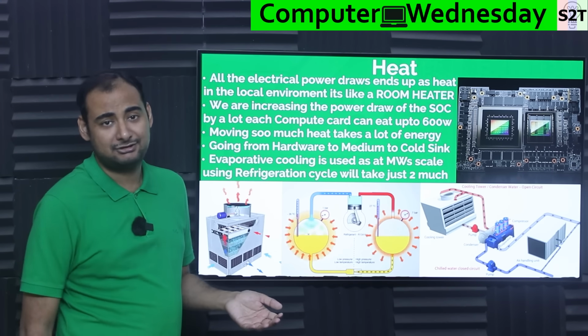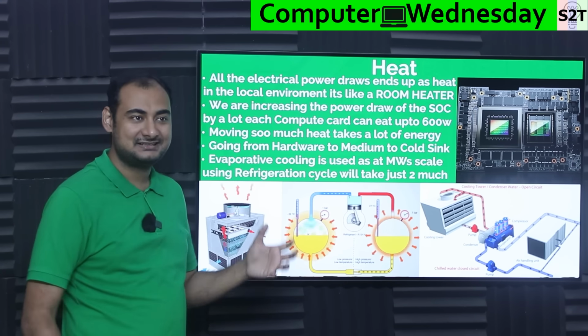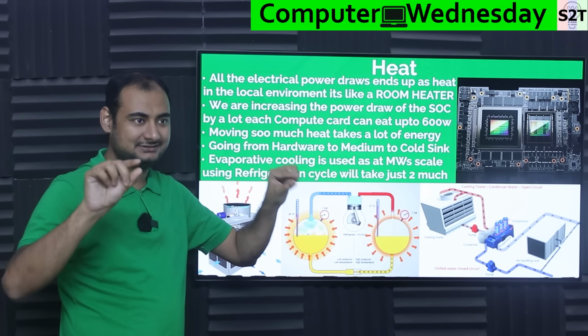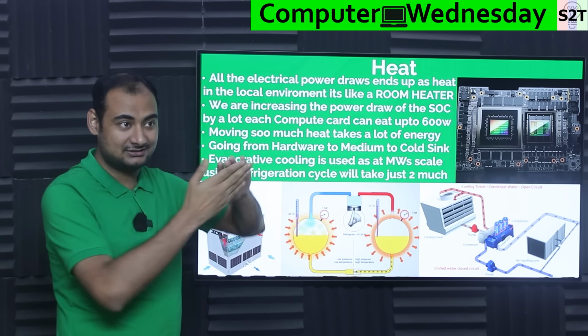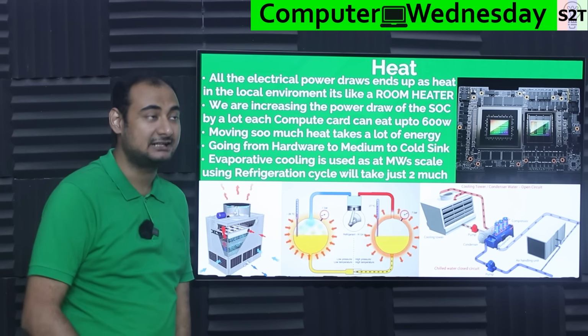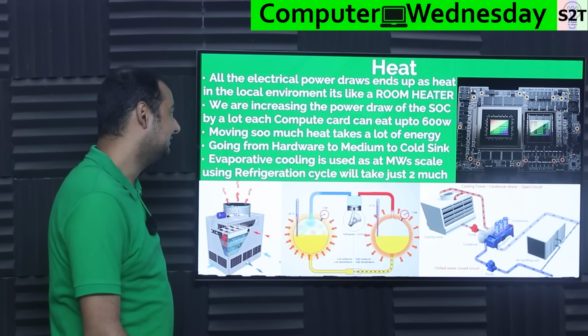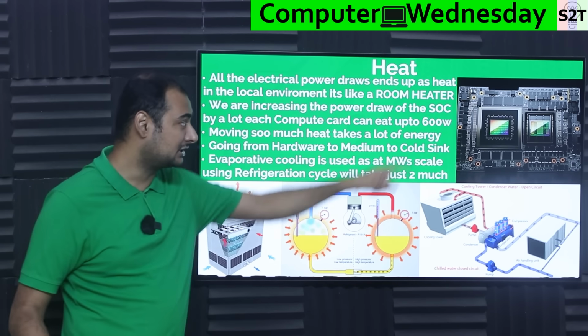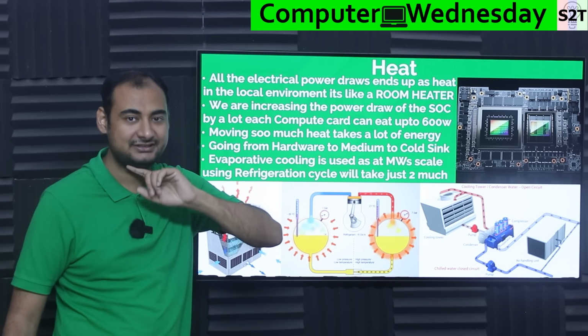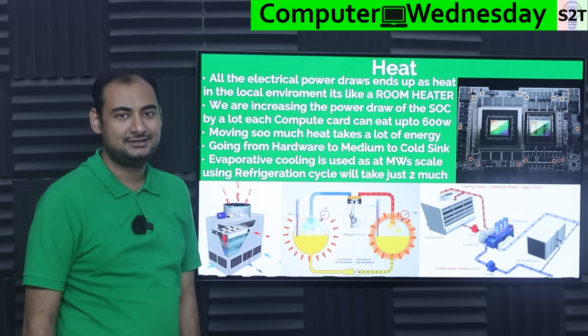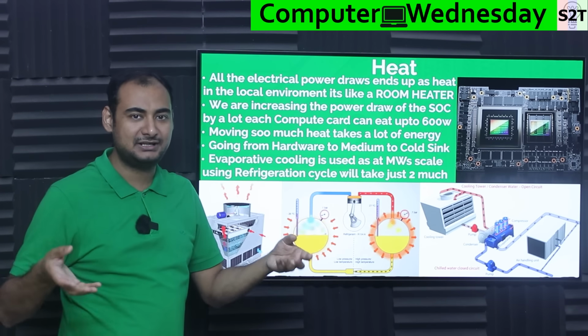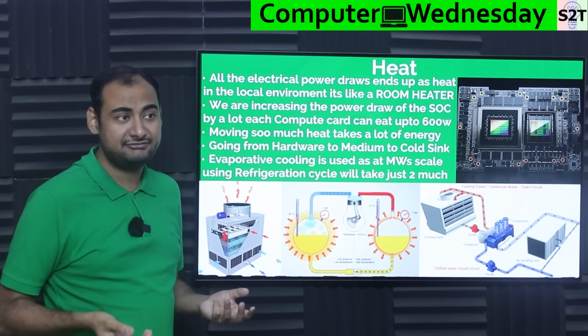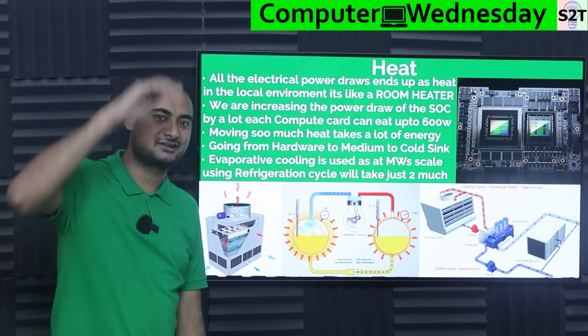We are increasing the power draw of the SoCs. Back in the days, the amount of power each blade is consuming right now was enough power for the whole rack. Power draw has gone bonkers. We are reaching a point where each compute card itself is consuming 600 plus watts. There could be 4 compute cards in one blade, and as high as 25, if not more, blades in one rack.